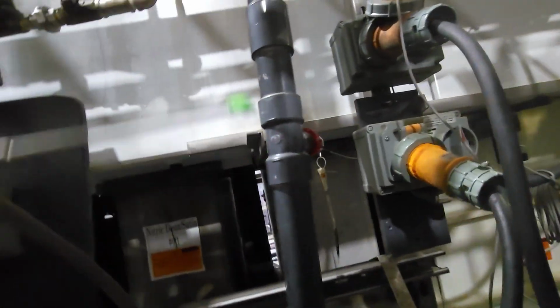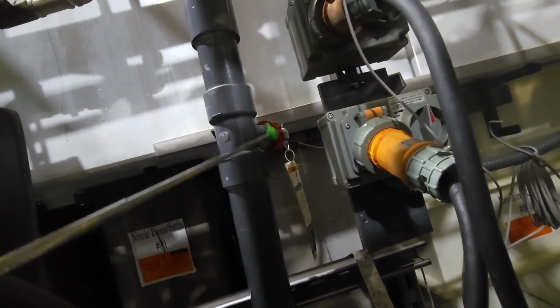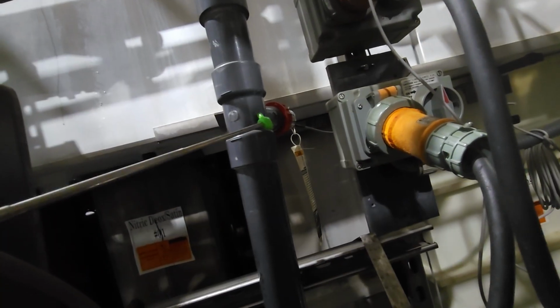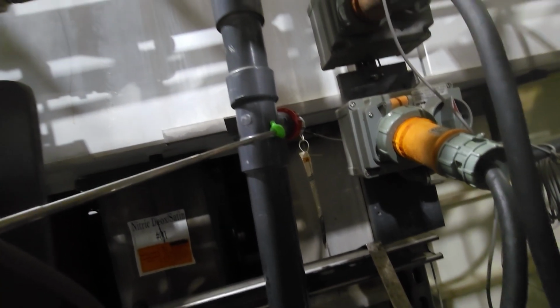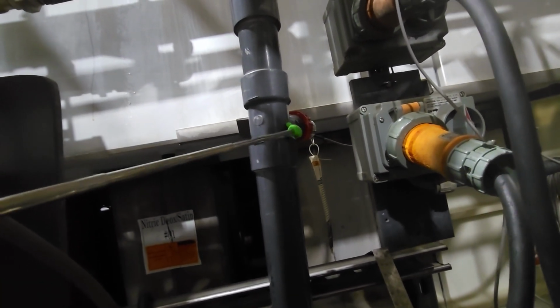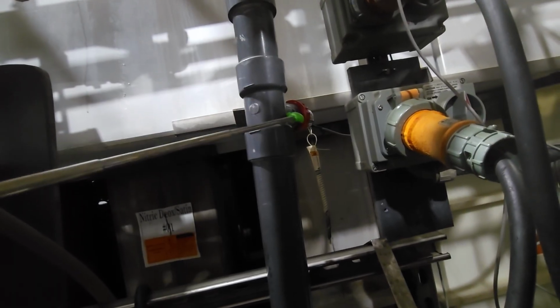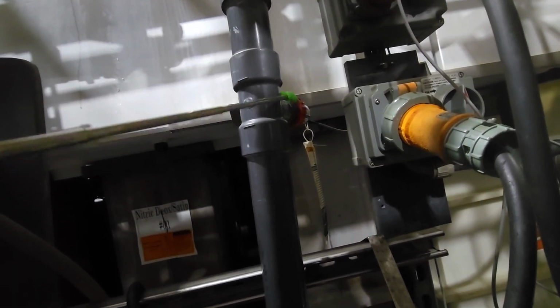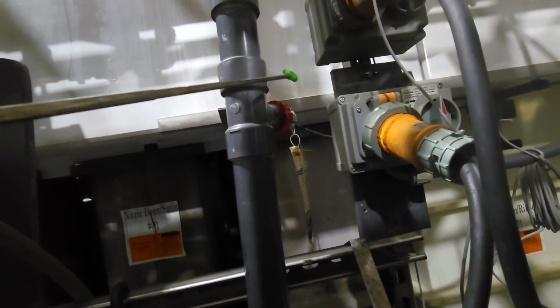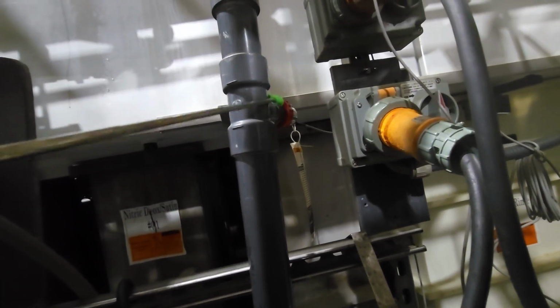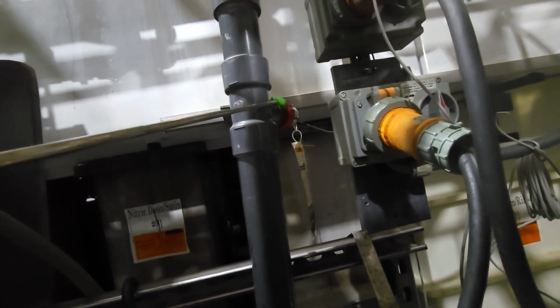But what tells us on SCADA is the flow sensor. Sometimes these can get junk gummed up in here and block flow, but not usually. Usually that ball barely sticks out in there. There's a little paddle that sticks out just enough to detect flow. If you're getting no flow alarms, things like that, it could also just be your flow sensor. As long as your system is working, you've got time to troubleshoot and fix it.